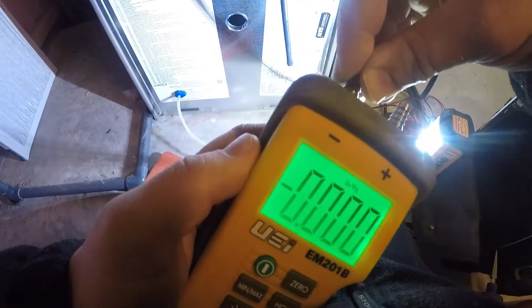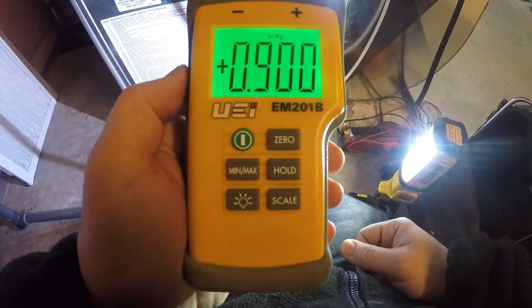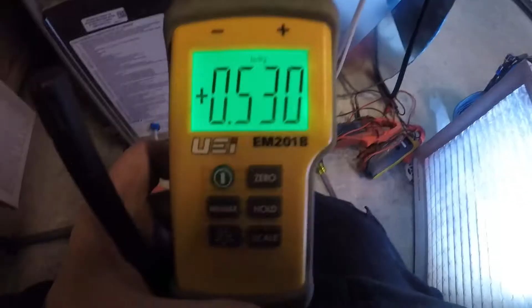So, return static. Wow. What is going on there? That's ridiculous. That makes no sense. Got 0.2 on my supply, but look at how crazy my return is. 0.8. So let's see what's going on here. Smooth filter, as you can see, and my return side is still 0.5. Pretty damn high.